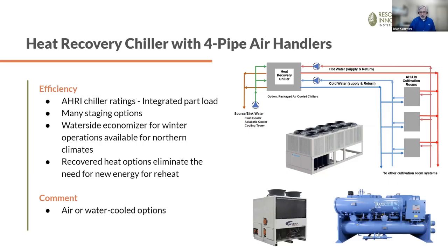I would probably recommend in this kind of application, not these large chillers because they don't provide much redundancy. If you have just one large chiller and it croaks, your entire facility is dead. I would go with maybe a modular arrangement, a number of chillers of a certain size, then you can have an extra 1 or 2 chillers just in case one of the modular units goes down, and make 1 or 2 of them energy recovery to provide that free energy for the reheat. These units can be water or air cooled, and you see 2 air cooled options there.